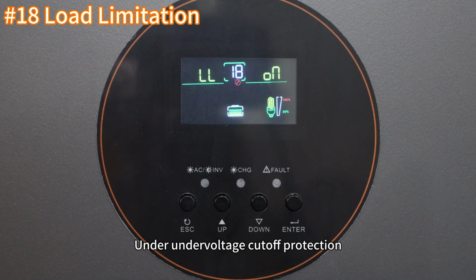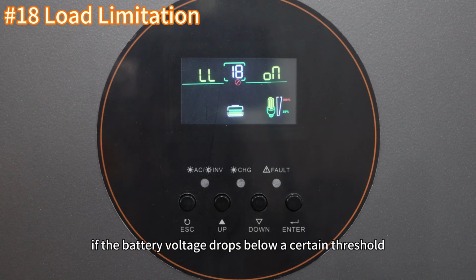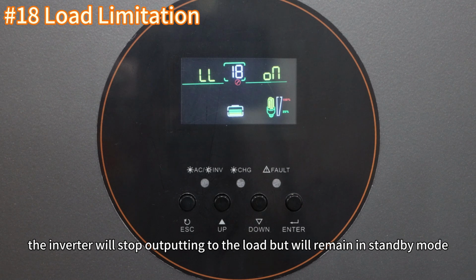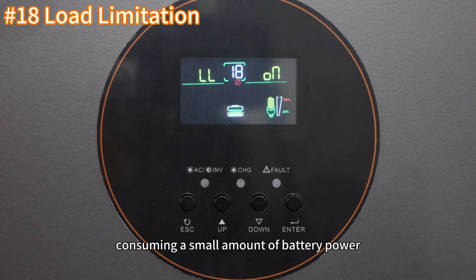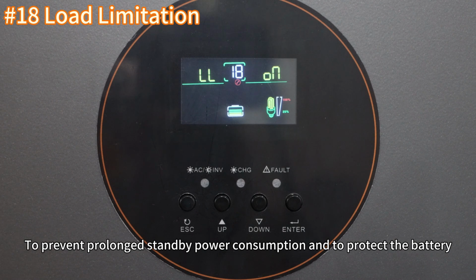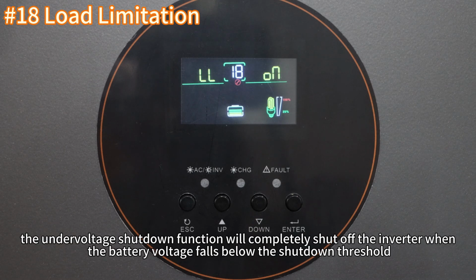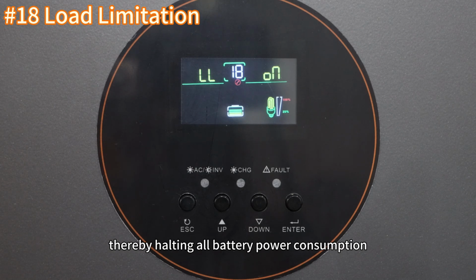Under undervoltage cutoff protection, if the battery voltage drops below a certain threshold, the inverter will stop outputting power but will remain in standby mode, consuming a small amount of battery power. To prevent prolonged standby power consumption and to protect the battery, the undervoltage shutdown function will completely shut off the inverter when the battery voltage falls below the shutdown threshold, thereby eliminating all battery power consumption.